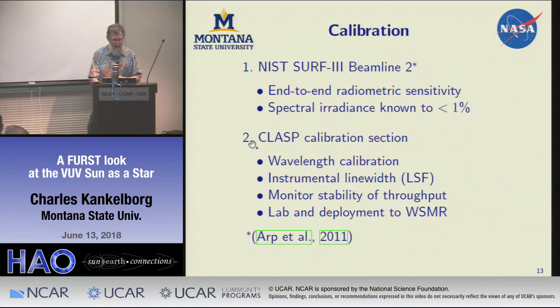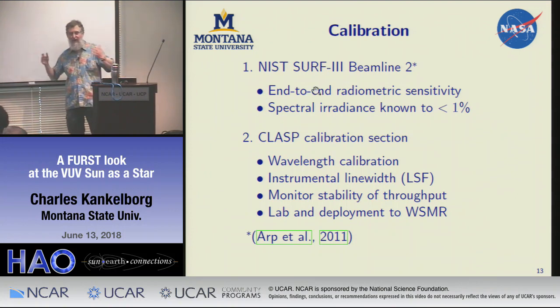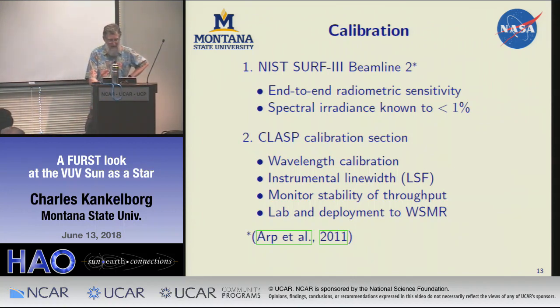Then the next calibration issue is wavelength, because the SURF 3 source, of course, is synchrotron, it's continuum. There are no spectral features whatsoever unless you stuff a filter in or something like that. So we have, as it turns out, because of my colleagues at Marshall Space Flight Center, this wonderful calibration section.